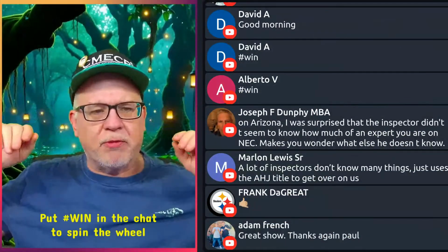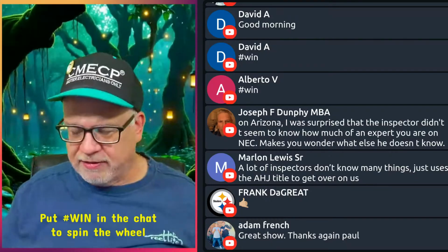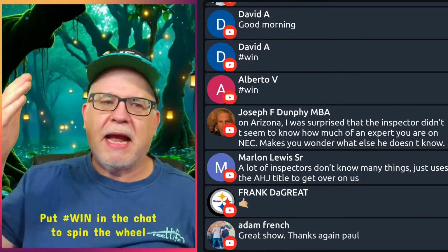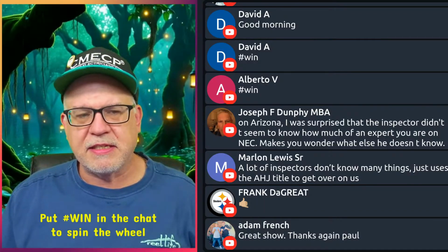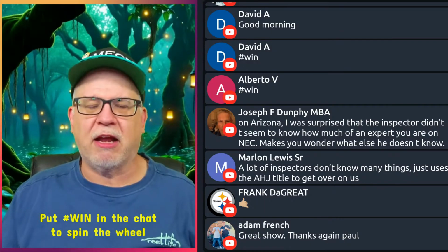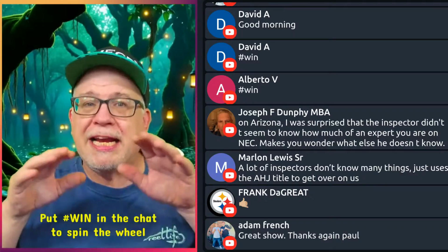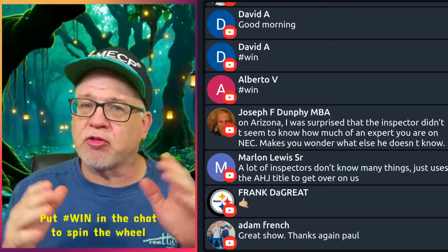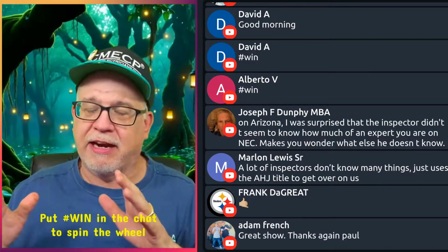Once it starts propagating all over social media, people's heads spin off. It's like you see a nameplate rating that says minimum circuit ampacity, maximum overcurrent device, overcurrent protection, and people freak out. Even though this is all based on Article 440. The rules are right in there that the manufacturers use to make these nameplates. It says it right there in 440.